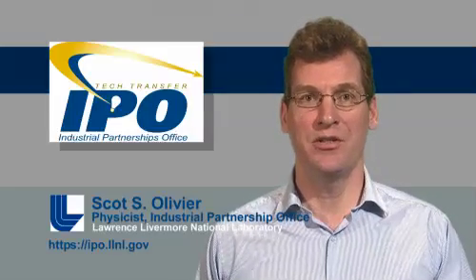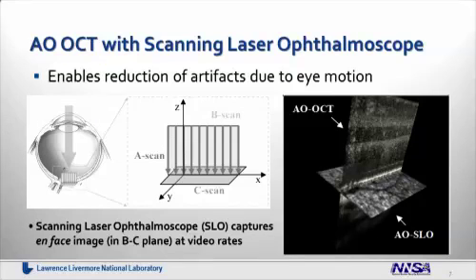A further invention here has been the combination of scanning laser ophthalmoscopy with adaptive optics optical coherence tomography. This enables the reduction of artifacts due to eye motion by taking high-resolution motion video at video rates of the back of the eye using a fast-scanning laser ophthalmoscope, combined with the adaptive optics optical coherence tomography imagery, which is taken at slower rates — typically several seconds to create a three-dimensional image. These combined techniques use fast motion video to capture any eye motions, which can then be post-processed to stabilize blurring effects in the slower process of capturing the optical coherence tomography image.